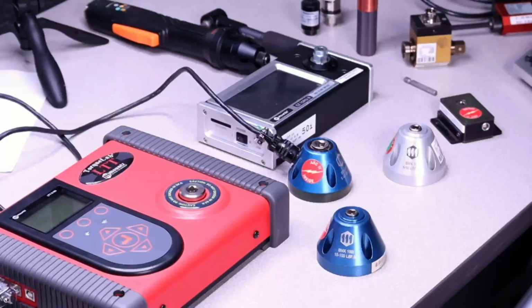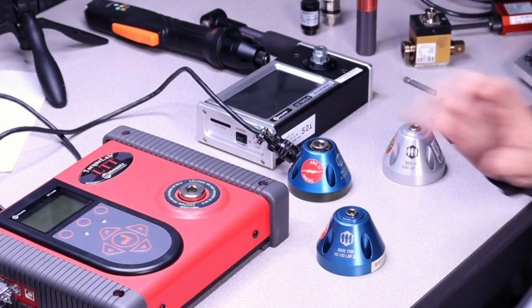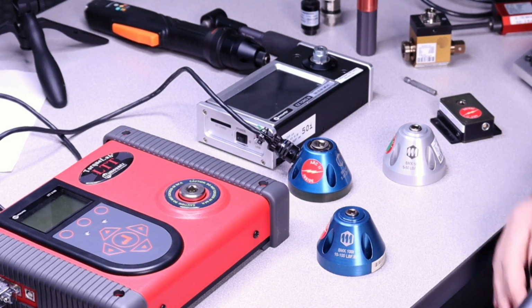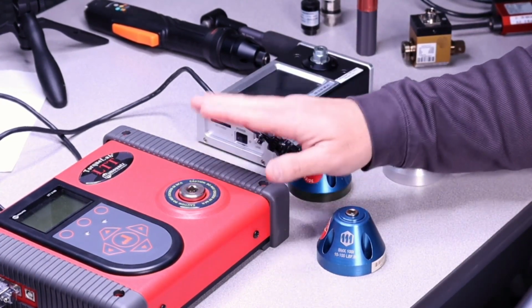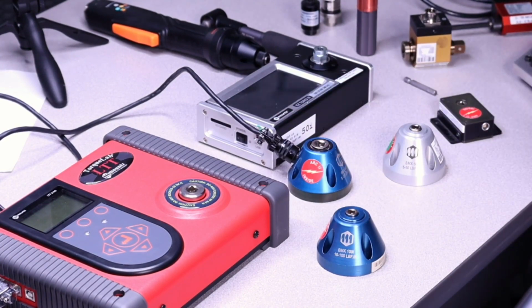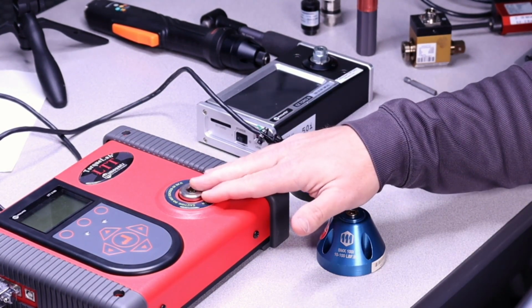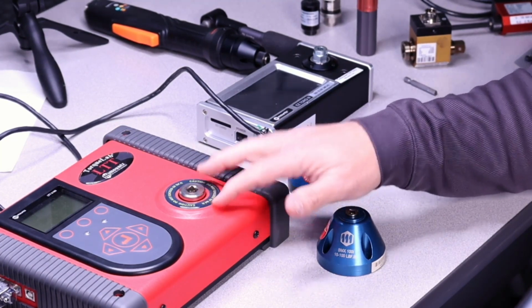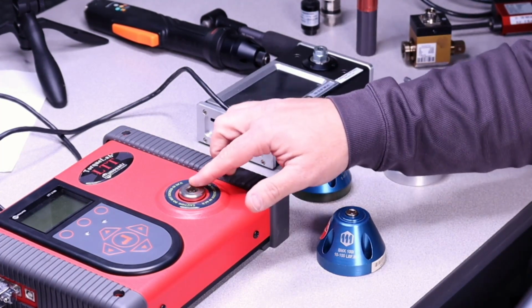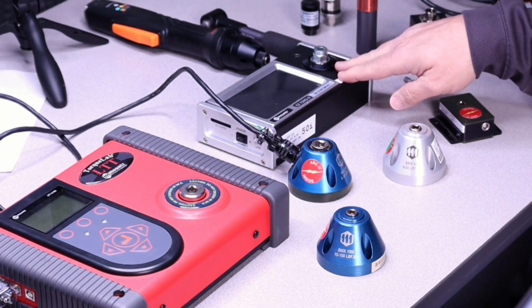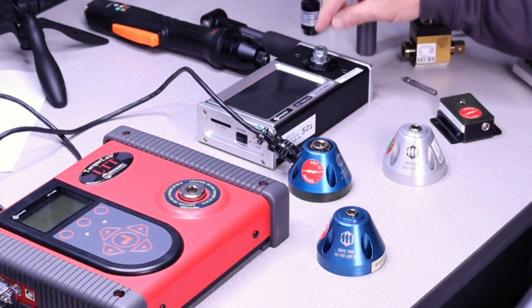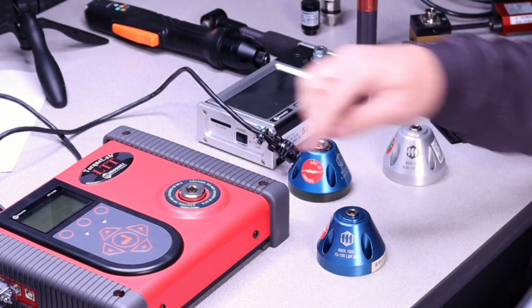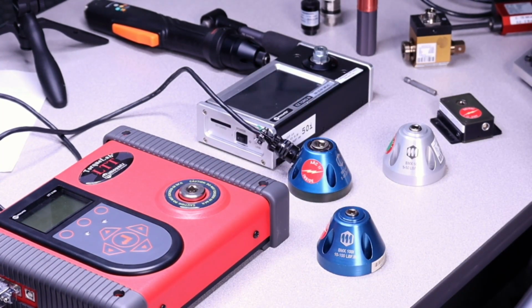So let's go ahead and take a look at the different reaction style sensors. On our gathering here of our different tools or sensors, actually, we have a couple different analyzers here, our LTT and our Easy Torque 3. Both of these analyzers have a reaction style sensor that is built into them, and they all have a certain range. So this one goes from 5 to 50 foot-pounds. This one goes from 5 to 50 inch-pounds. So these, again, we would be testing directly into the drive of the reaction style transducer.